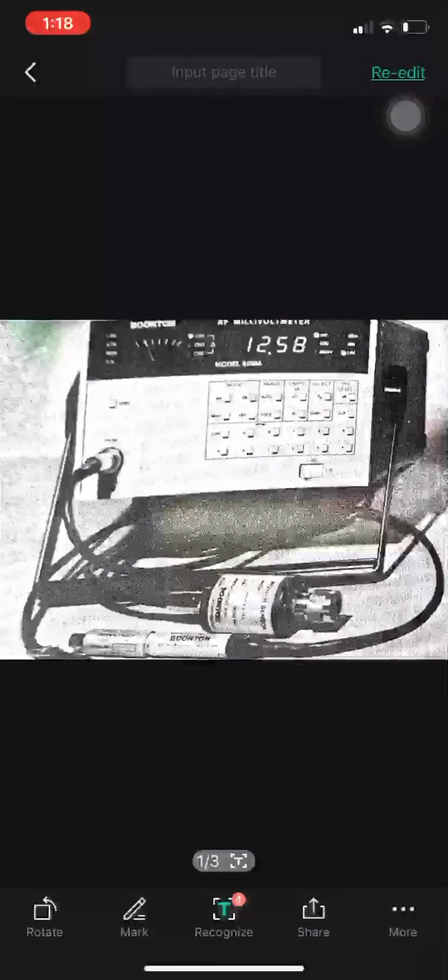or point contact diodes. After this, the second important point which I would like to bring into your notice is that we know that the rectified output has a peak lesser than the peak of the input, which means that the output needs to be amplified. For amplification of the RF waveform, we usually use a chopper stabilized amplifier.